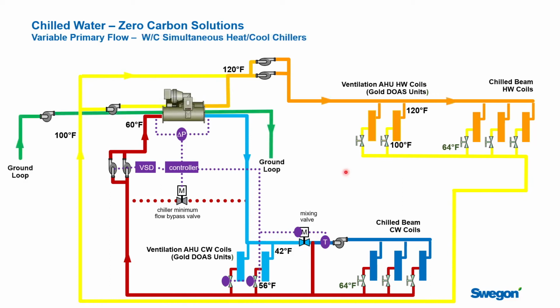Now we can do the same thing with a water-cooled plant. So the chillers would change. They'd now be 6-connection chillers like we just discussed. You'll see everything that we saw on the chilled water side is one set of loops. Where possible, we're going to take that heat and use it. If we have a demand for heating, we'll take the heat out of the building, raise its temperature, and deliver that water out to the building to do the heating. Could be around the perimeter.